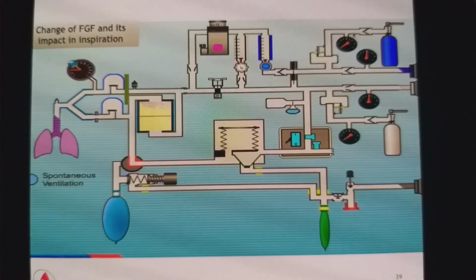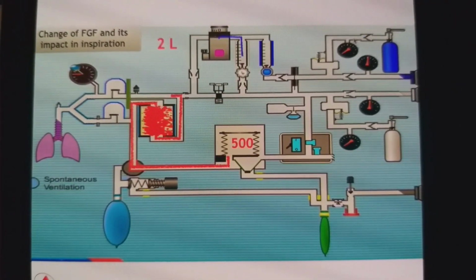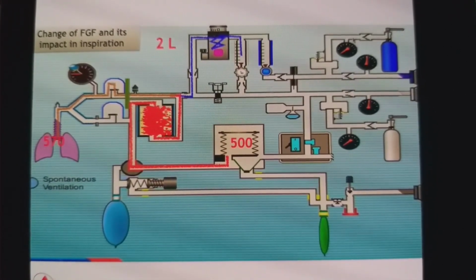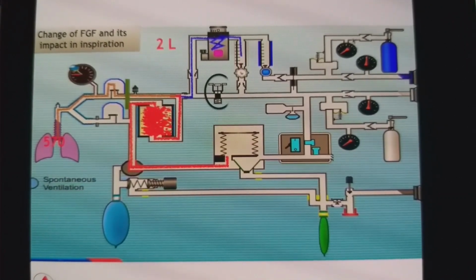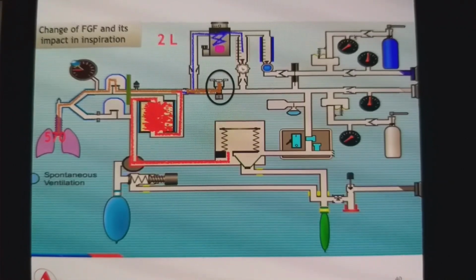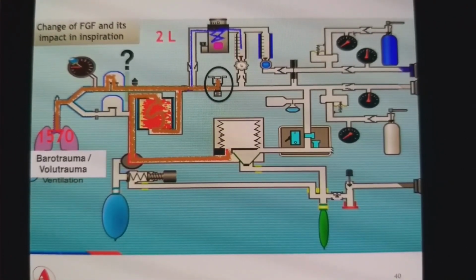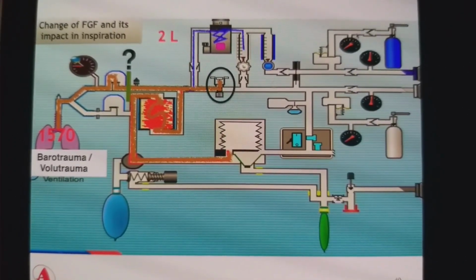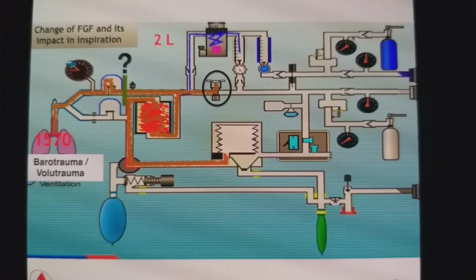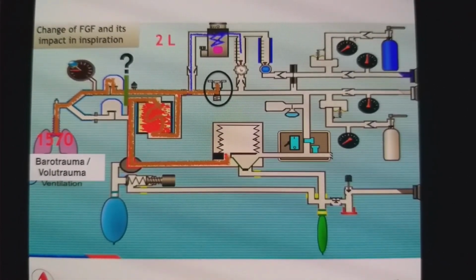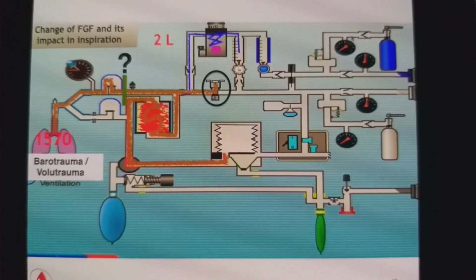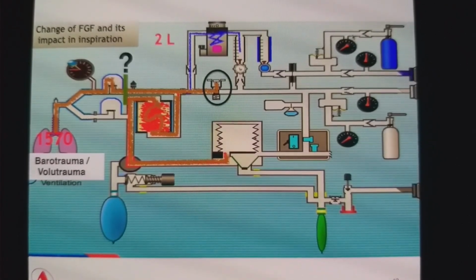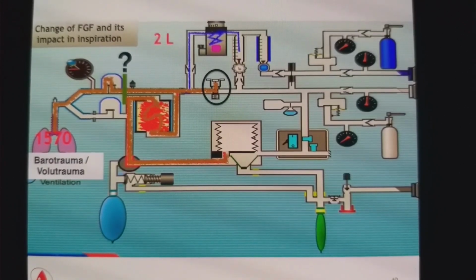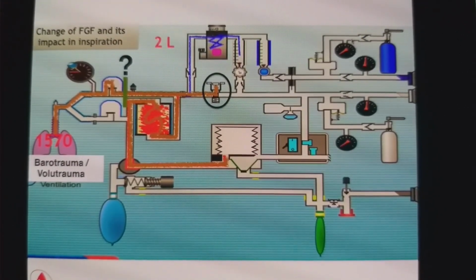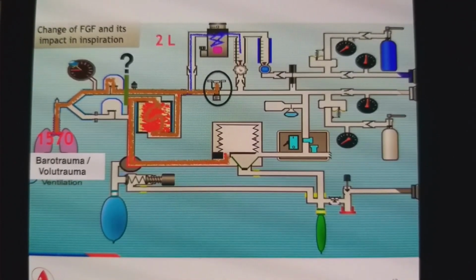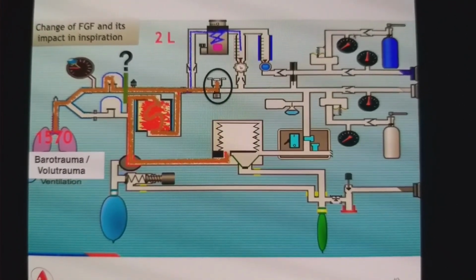Now let's see what will happen with the bellows circuit, where fresh gas compensation is a technology. Now here, my bellows are going down and I want to use flush. I don't want to use flush, but if I use flush, what will happen? When you press flush, the flow is almost 35 to 40 liters per minute, and within 2 seconds, probably what will be delivered is 1000 ml. Now that will go to the reservoir, but also will directly go to the inspiratory line, because there is mixing of fresh gas flow into the inspiratory line. So it is possible that your patient for that breath is going to receive almost 1 liter, 1.2 liters, 1.5 liters. So very large amount of flow is delivered to the patient, which can cause barotrauma as well as volume trauma.